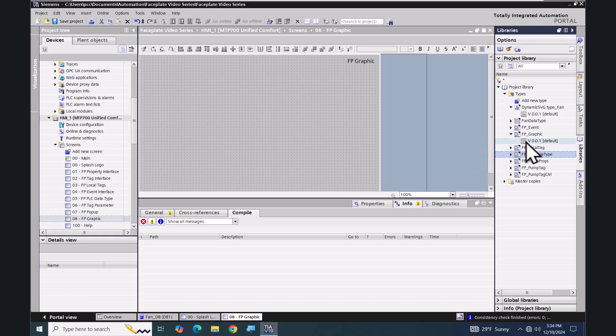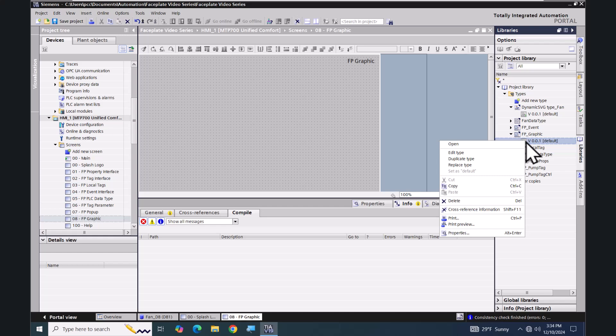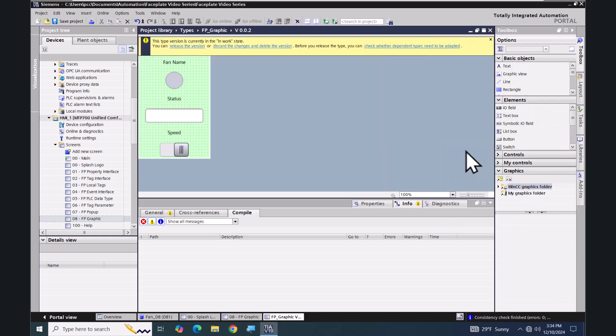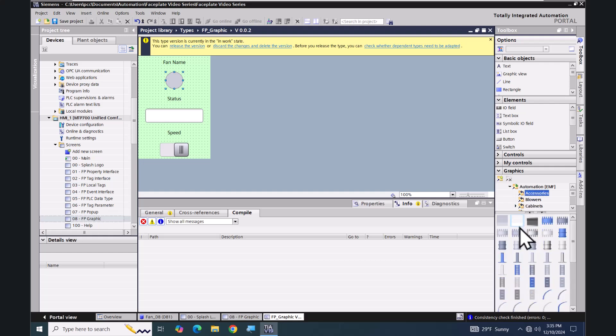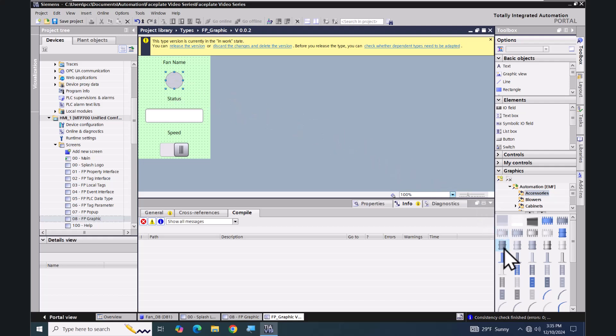I'm going to right click on the fp underscore graphic faceplate and select edit type. In a previous lesson we used this circle object to display the status of our fan. You will notice that in our toolbox there is not a folder for dynamic SVGs, so they cannot be directly brought into a faceplate. You do have access to the actual WinCC graphics folder, but if you try to bring in one of the objects it's not going to allow you. So you have to create a type — whether it's a graphic or a dynamic SVG — and have it managed in the library to use it inside the faceplate.